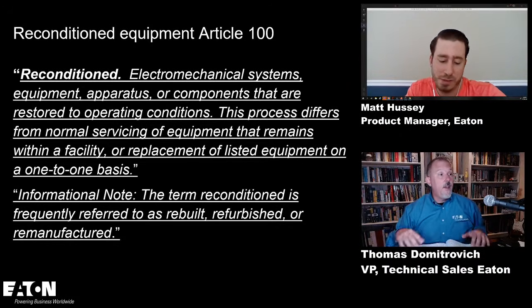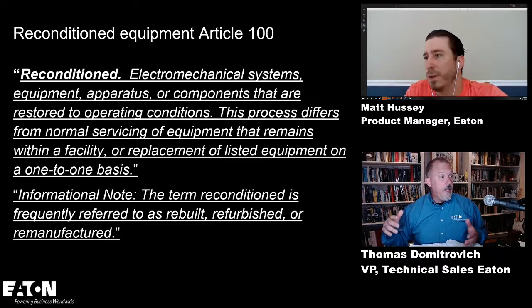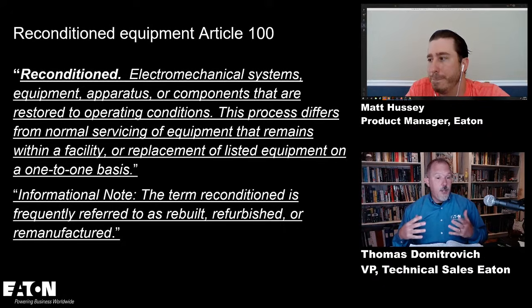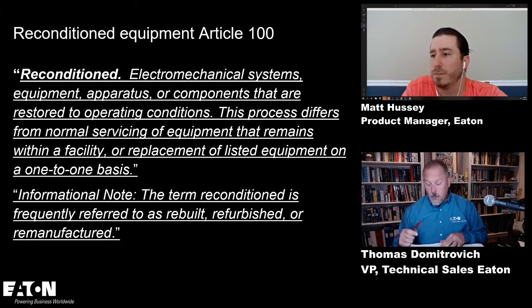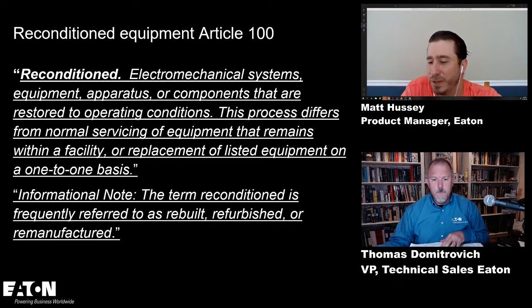So think that, if you had an arc flash event in one of those cubicles, and you're going to take everything out and get it all back up and running again, you're questioning how do you know the integrity of the bus, the way the bus is installed and connected, the insulation that might be in there, and other areas of that MCC. Good point. Because once you recondition it, you can't do a field short circuit test or anything like that. Nope, those are failure tests.